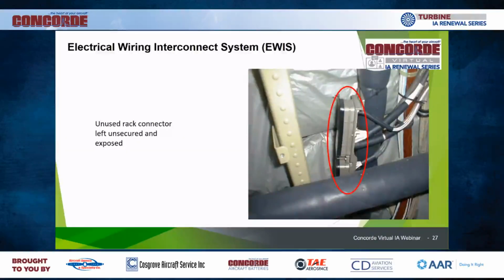There are many times when retrofits and modifications require removal of equipment. That removal may take out the rack or the device itself, but sometimes the wiring remains. In this case, they found a connector that would normally have connected to the back of a rack — the wiring and connector remained, but the rack was gone. So there's possibly exposed power still going to this connector. It should have been depowered, of course, but who knows — in this case, it was just hanging loose.